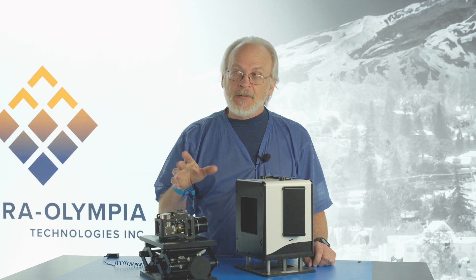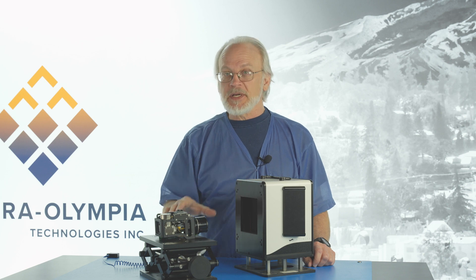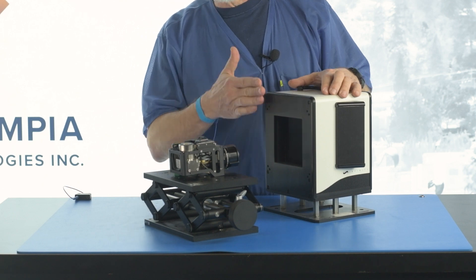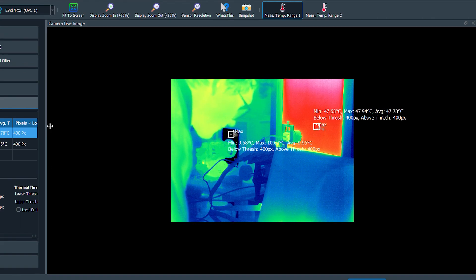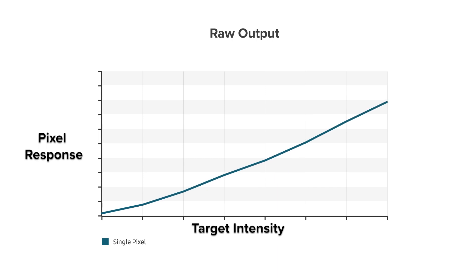What's a NUC — a non-uniformity correction? That answer has two parts. The first part happens at our factory in the test process on our cameras. We use this area black body, which is a device that's able to show a uniform scene to the sensor, and we can vary that temperature to give it different intensities. We can plot the intensities on the x-axis and the response of the pixel on the y-axis, and we can find the characteristic of that one pixel and plot it.